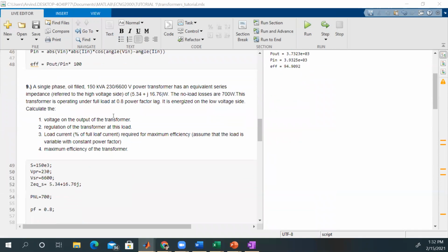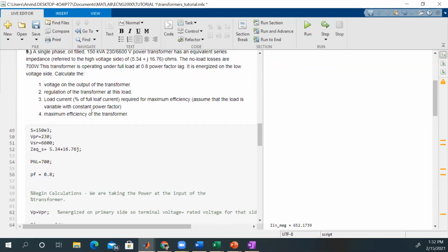So now on to number 9. We have a single phase oil-filled 150 kVA, 230 to 6600 volt power transformer with an equivalent series impedance referred to the high voltage side, the secondary side this time, of 5.34 plus j16.76 ohms. No load losses are 700 watts. The transformer is operating under full load at 0.8 power factor lag, energized on the low voltage side. Now we want to find the voltage on the output of the transformer, the regulation, the load current, the load current required for maximum efficiency, and the maximum efficiency of the transformer.